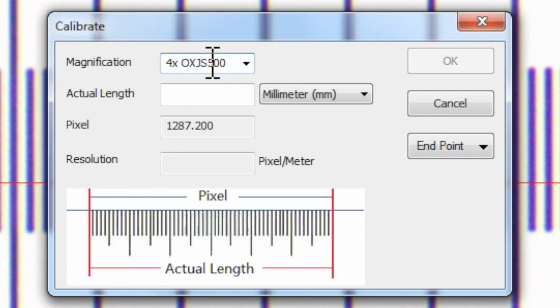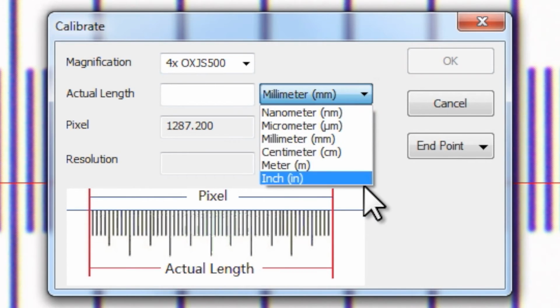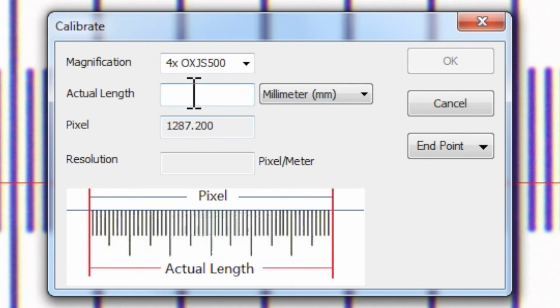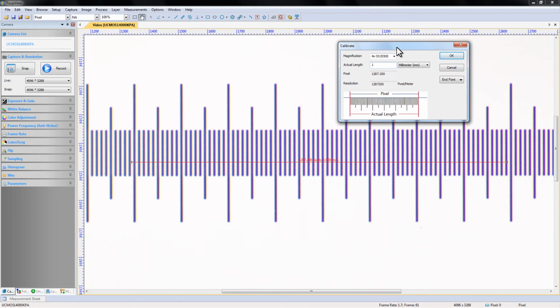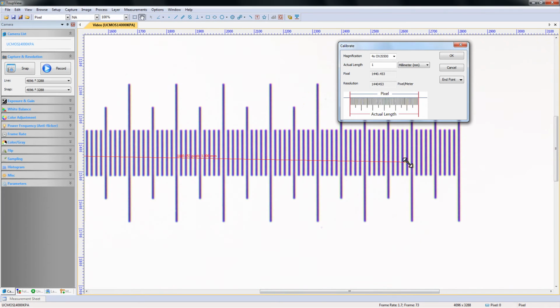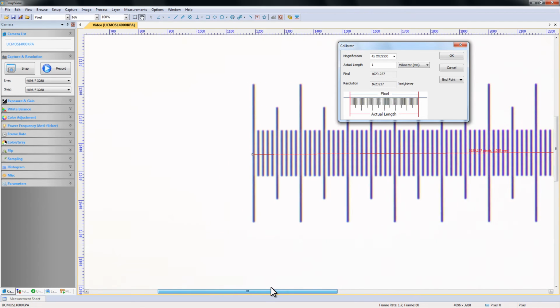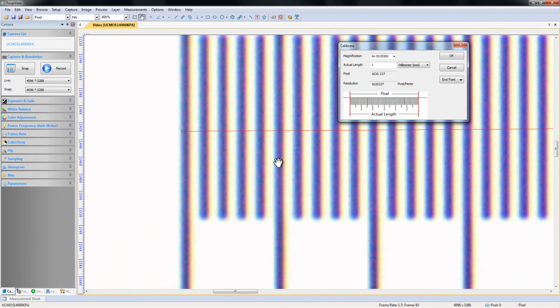It is now requesting the actual length being calibrated. In this example, we're using a low magnification objective lens, so we're going to calibrate using the full length of the stage micrometer, which is 1 mm. If you are using a higher magnification objective lens, then calibrate using the micrometer divisions. You will notice that a red line has appeared over the image. Drag one end of that line to the start and the other to the end of the stage micrometer. At this point, you can increase your digital magnification to more accurately position these markers, but return it to 100% magnification afterwards.